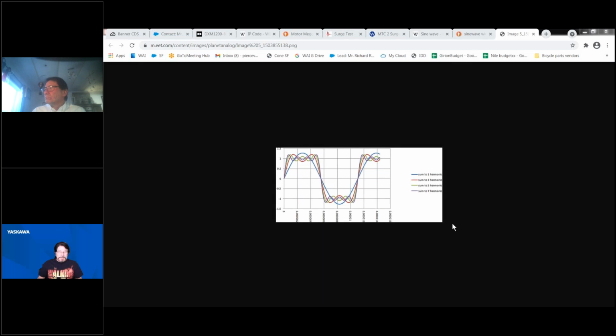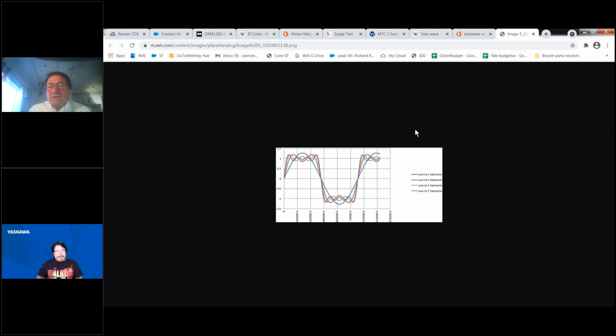So then the motor manufacturers, or the submersible manufacturers, came up with, well, let's encapsulate the windings. So we're going to lose the cooling effect of the water circulating around the windings, because the water in contact with low VOC varnish was causing it to soften up. Well, they encapsulated. Just a second, Craig.